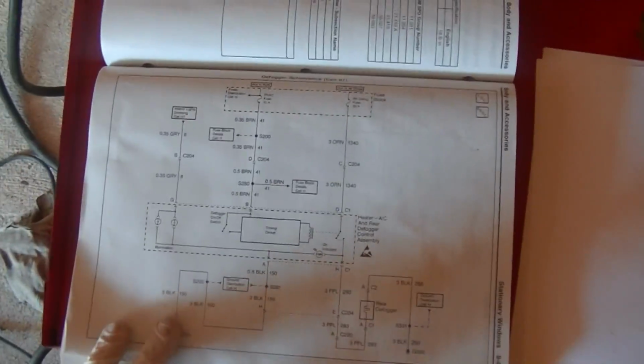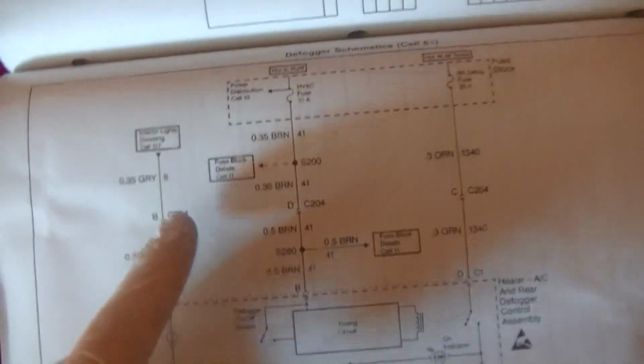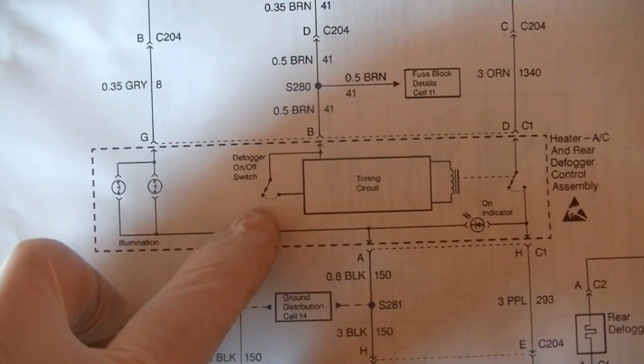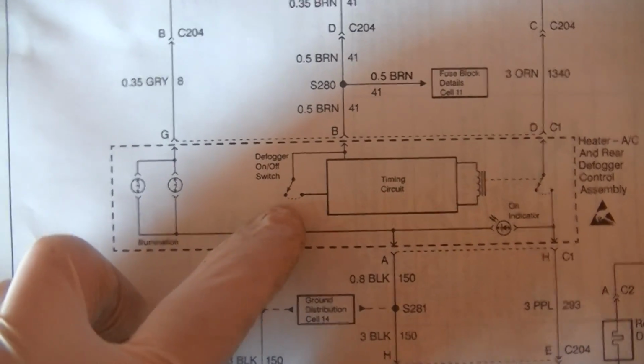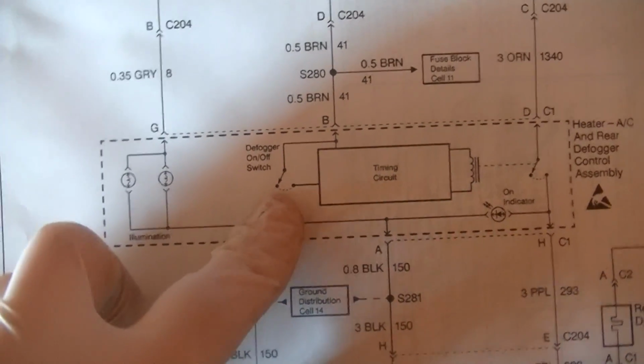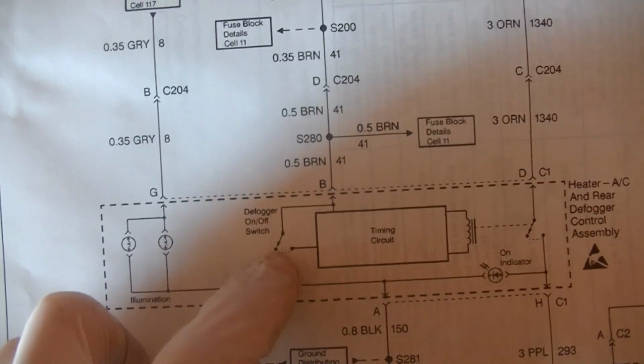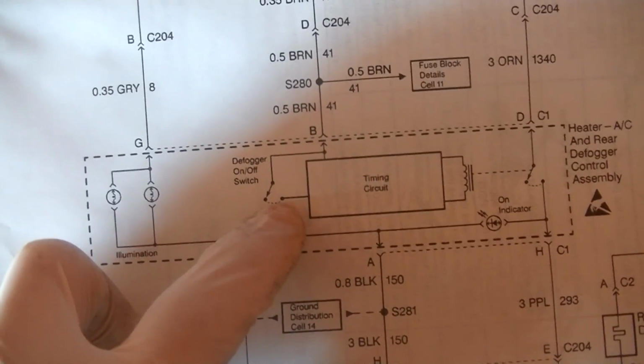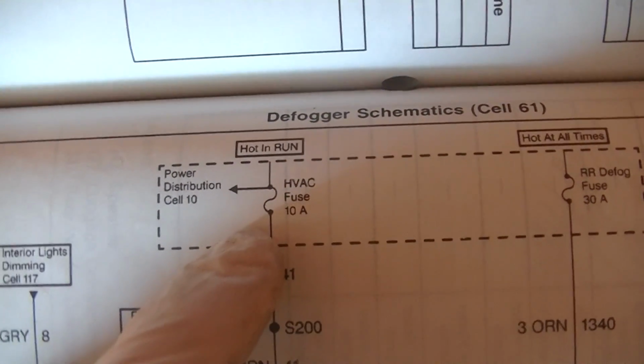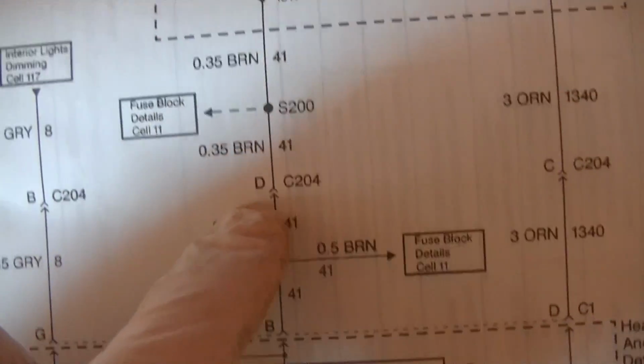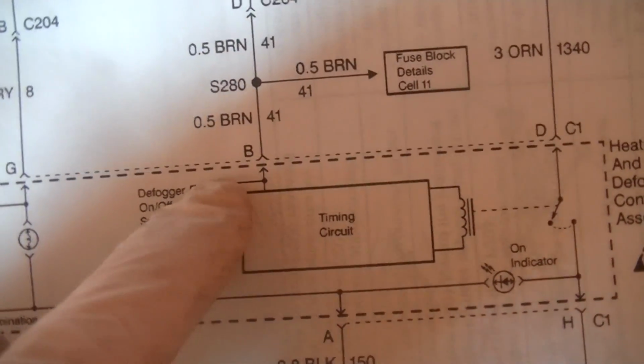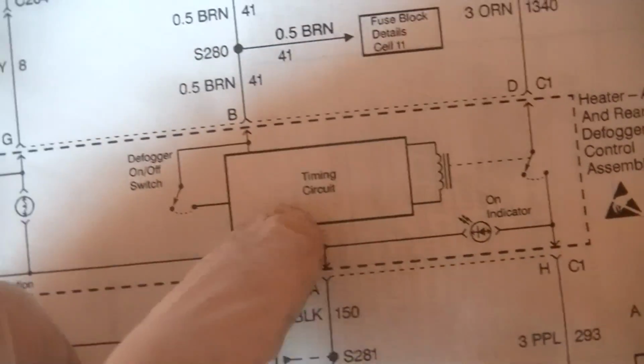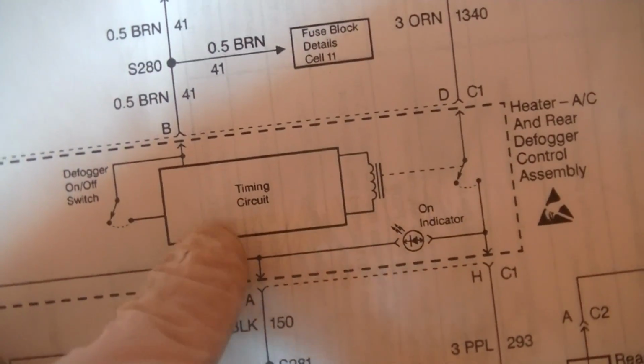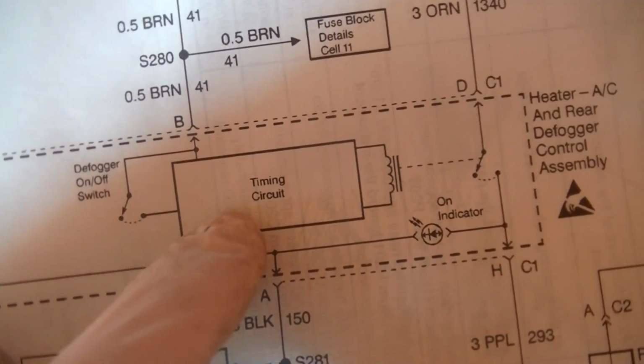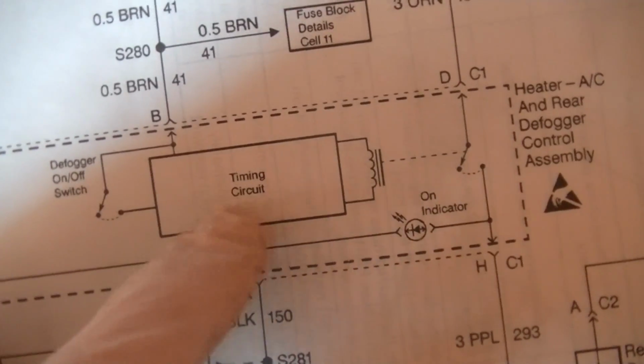So here's the wiring diagram for this circuit. This right here is the switch on the console, or the button. So you press the button, it closes this contact. Now current can flow through this fuse, which is hot in run. It goes through this fuse, through the timing circuit. This is the thing that will shut off the heater after a certain amount of time.